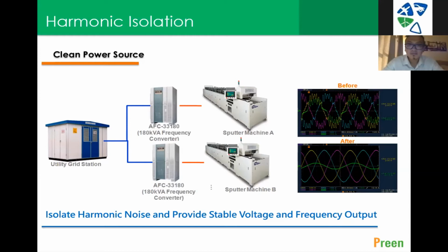Most people think it's maybe not a big deal, but some have had problems in the past: I turn on machine A, but machine B cannot work. When I turn on machine C, machine D cannot work. That's because of the harmonic noise. Most of the time, it's harmonic noise, because when you turn on that machine, it generates a lot of harmonic noise and makes the other machine unable to work. So in our experience, we recommend customers who have machines that generate a lot of harmonic noise put the AFC in front of it. Because the AFC is AC to DC and DC to AC, it will isolate the harmonic noise.